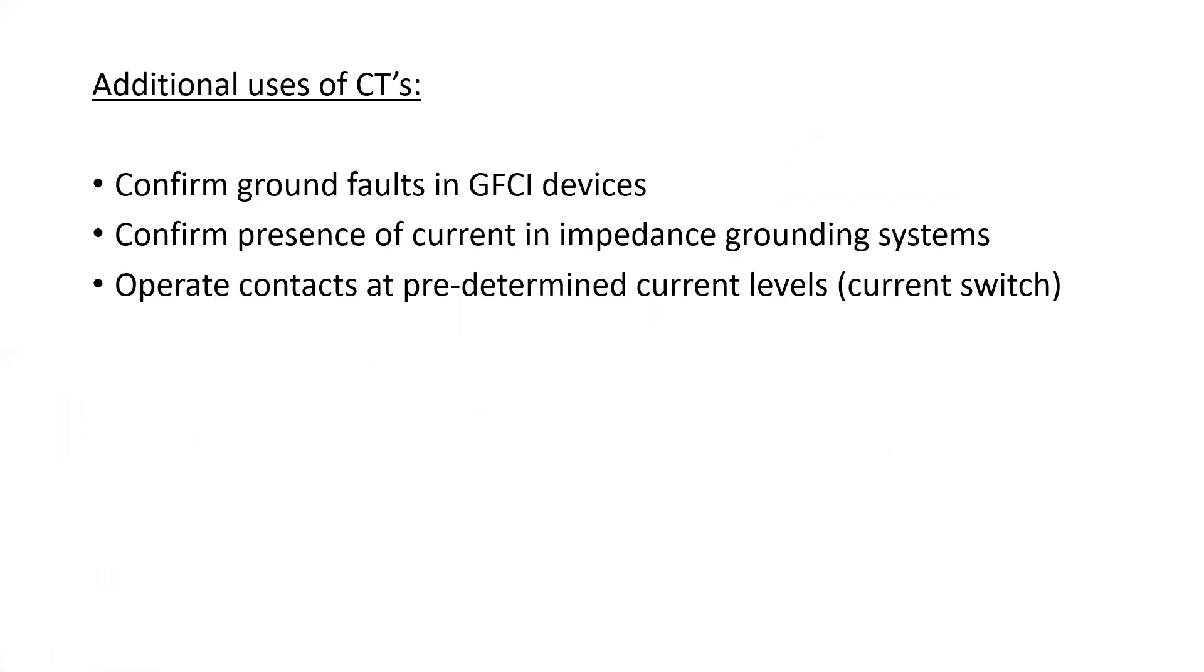So what additional uses do we have of CTs? Well, we can confirm ground faults in GFCI devices. We can confirm the presence of current in impedance grounding systems. And we can also operate contacts at predetermined current levels, which is often known as a current switch. These are just some of the additional uses of CTs. There are far more out in industry.